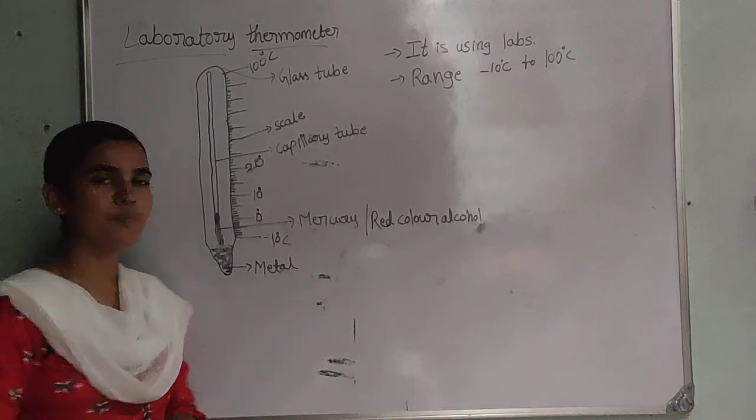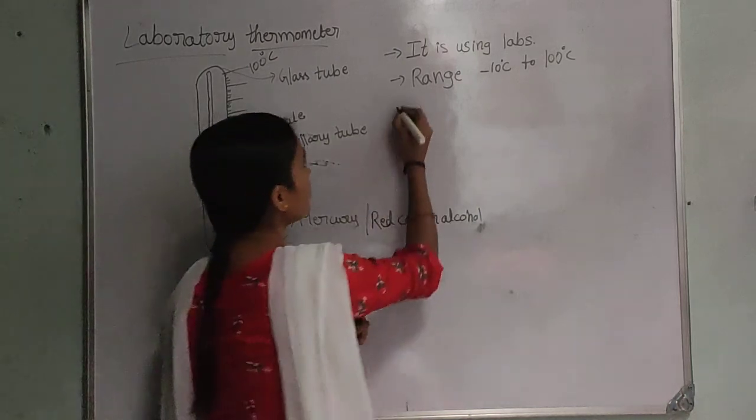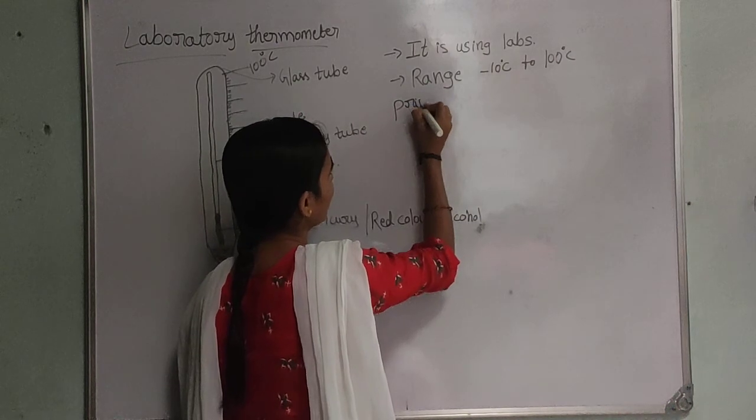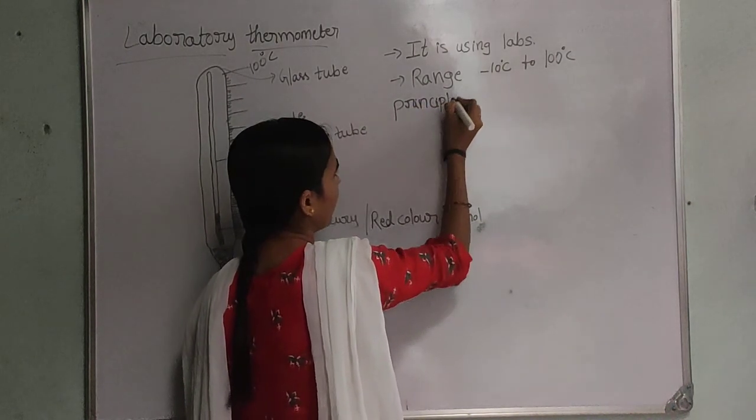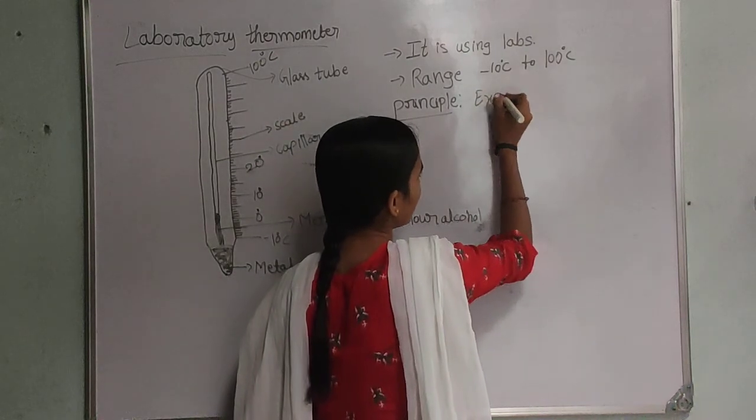So this is about the construction. Now, working: how is it supposed to work? Its principle is, we already know, that the laboratory thermometer works on the principle of expansion of liquid.